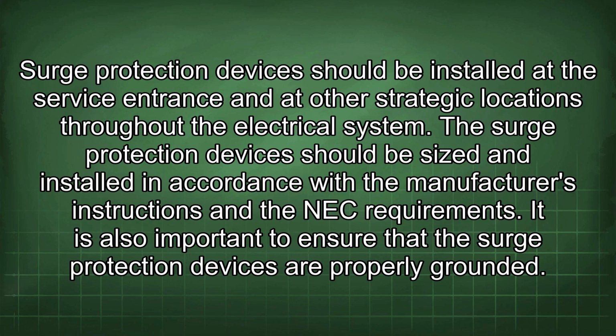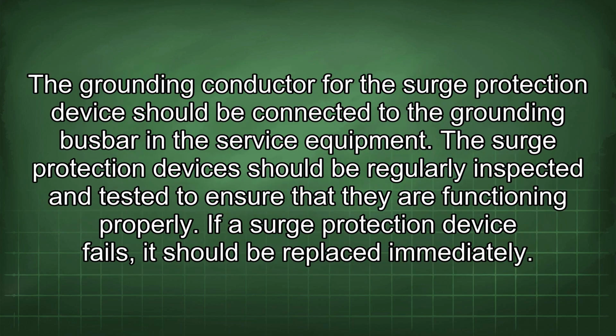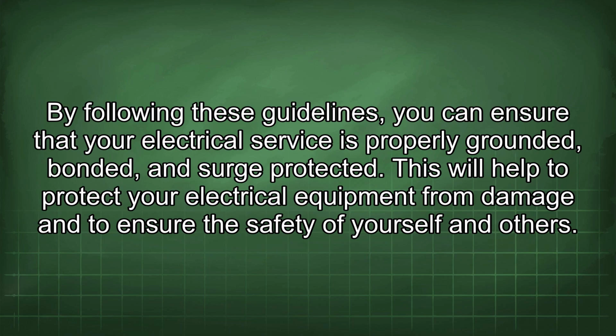It is also important to ensure that the surge protection devices are properly grounded. The grounding conductor for the surge protection device should be connected to the grounding busbar in the service equipment. The surge protection devices should be regularly inspected and tested to ensure that they are functioning properly. If a surge protection device fails, it should be replaced immediately. By following these guidelines, you can ensure that your electrical service is properly grounded, bonded, and surge protected. This will help to protect your electrical equipment from damage and to ensure the safety of yourself and others.